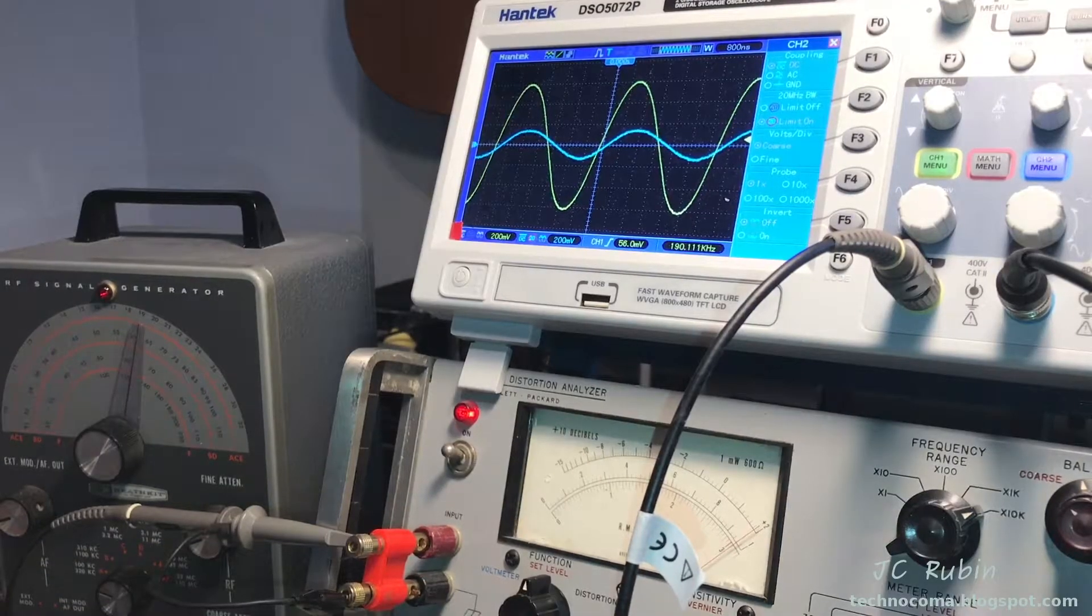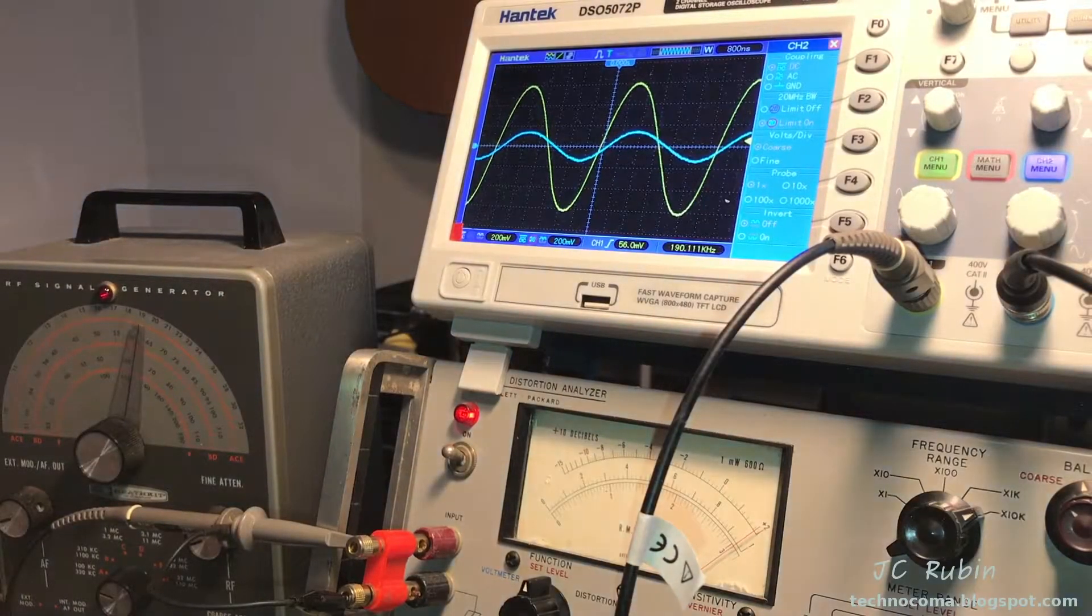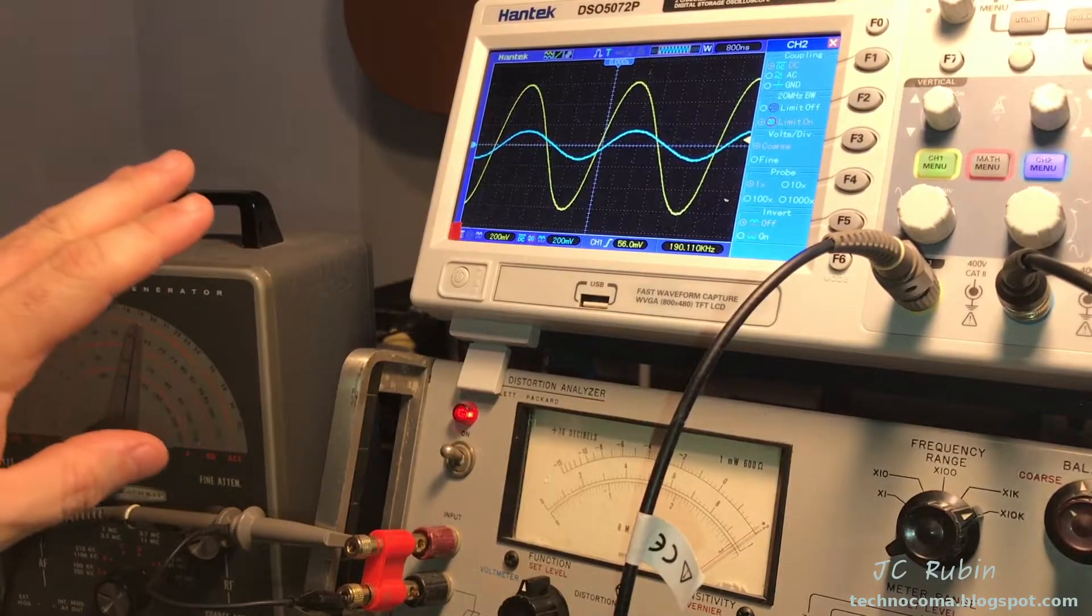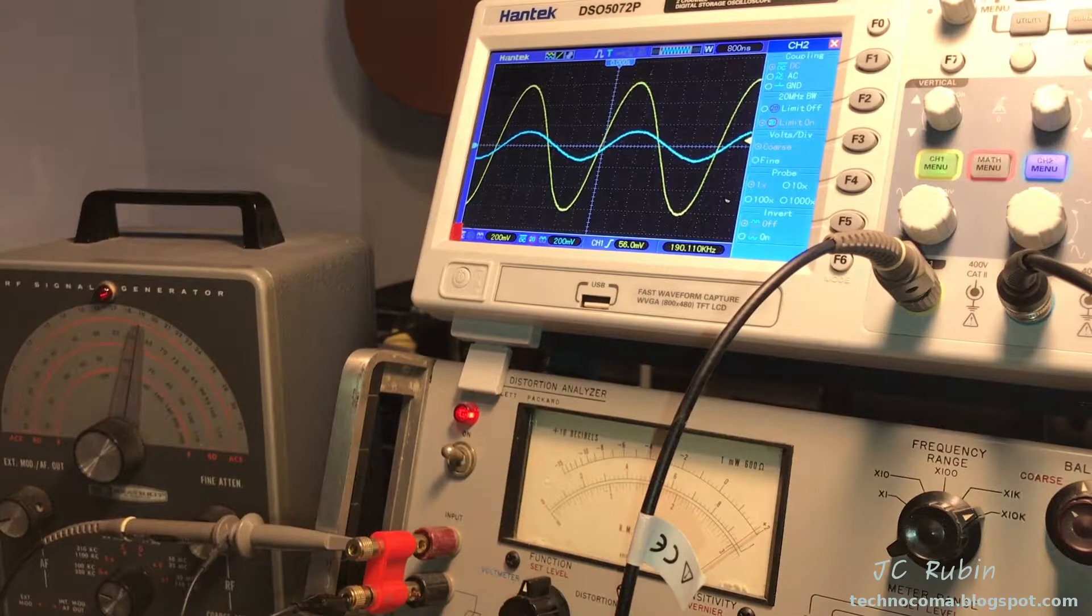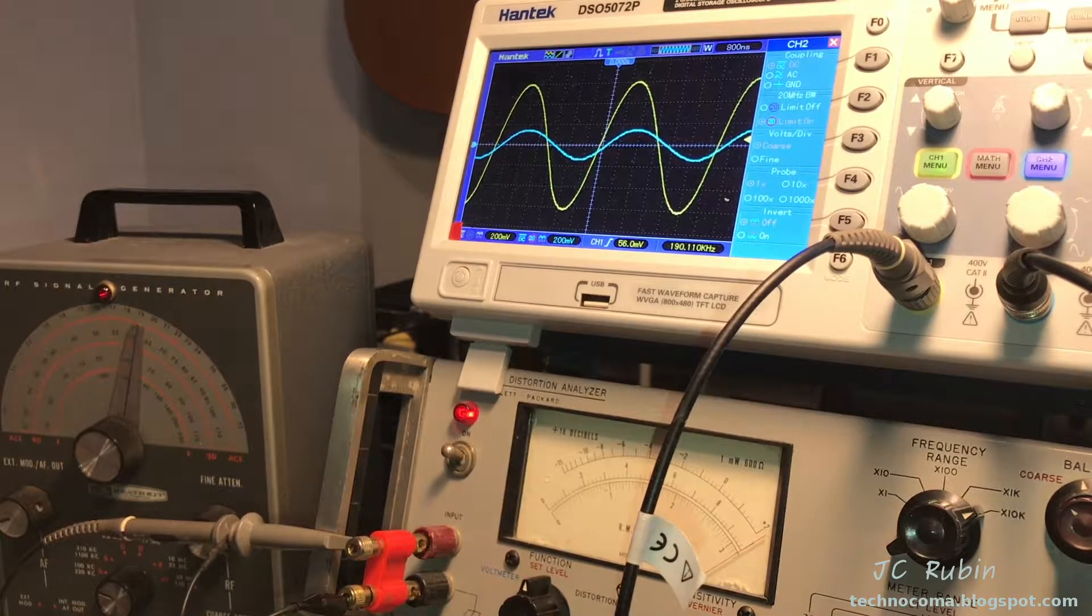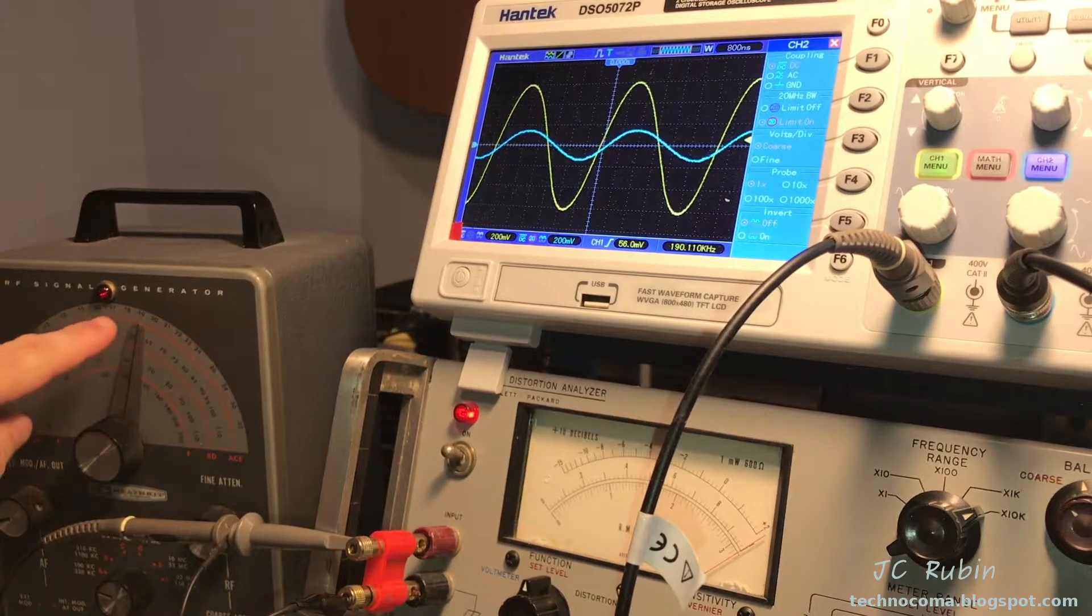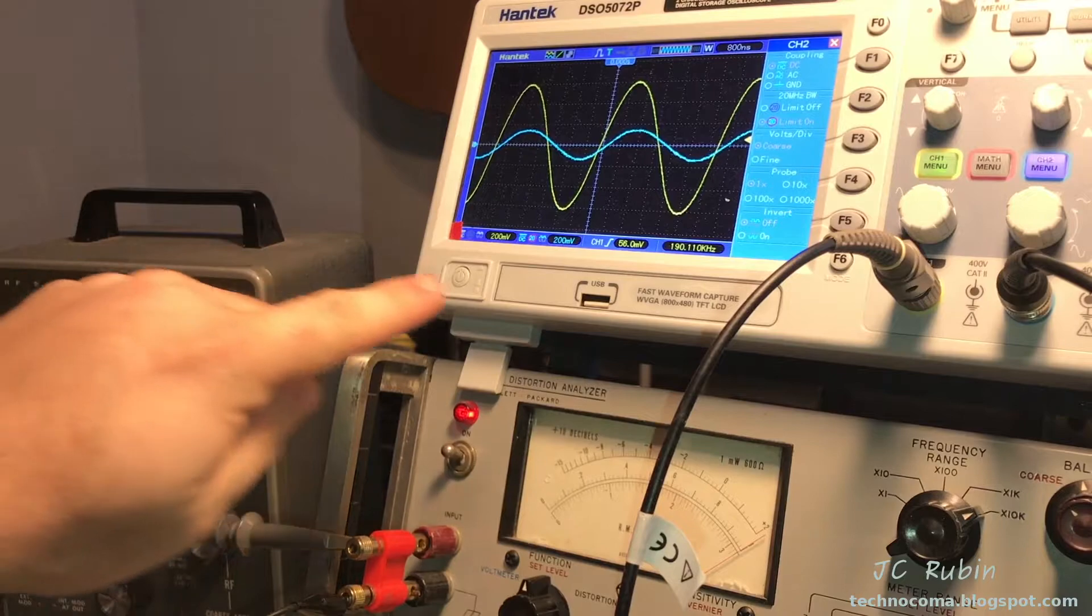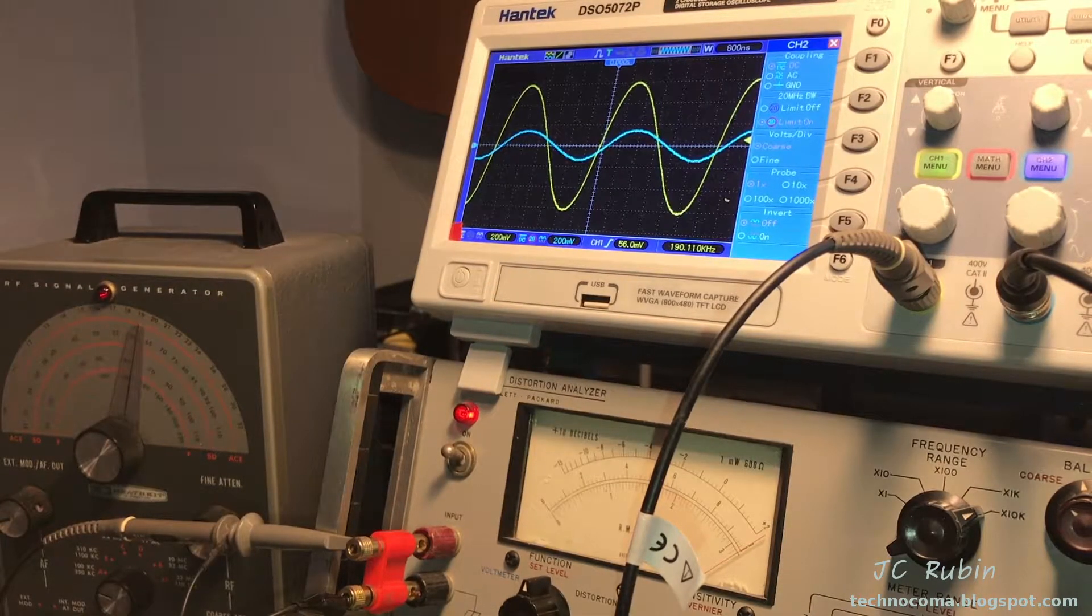We're going to use the same three frequencies from the last test with the TSG17. I'm now getting more than enough voltage to drive this to full deflection. I'm just setting it up right now. Now it's at full deflection and I've also set this up for 190 because that's what we used last time. With that we can get started with our first test.